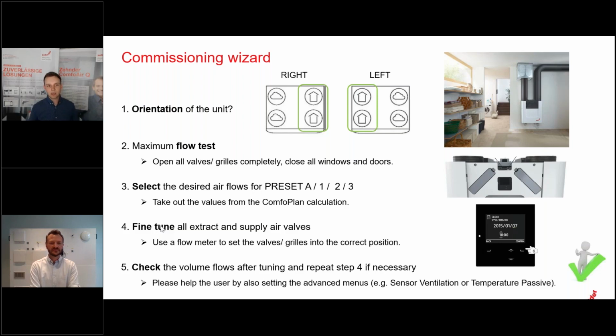The next step is the maximum flow test to find out the maximum flow. This varies with the system pressure drop. If you have long ducts and many bends, the maximum volume flow will be lower compared to a system with less pressure drop. When you are doing the maximum flow test, you need to make sure that all valves are completely open and all windows and doors are closed during the testing.